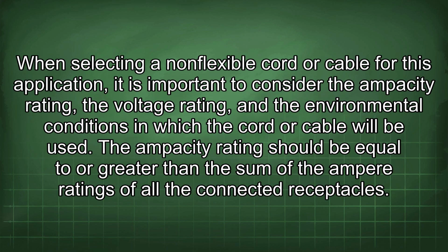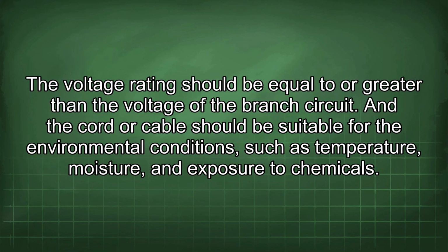When selecting a non-flexible cord or cable for this application, it is important to consider the ampacity rating, the voltage rating, and the environmental conditions in which the cord or cable will be used. The ampacity rating should be equal to or greater than the sum of the ampere ratings of all the connected receptacles. The voltage rating should be equal to or greater than the voltage of the branch circuit. And the cord or cable should be suitable for the environmental conditions such as temperature, moisture, and exposure to chemicals.